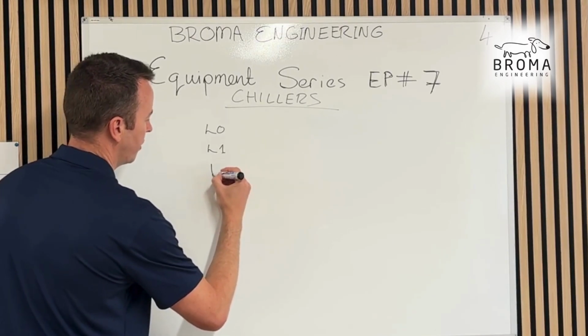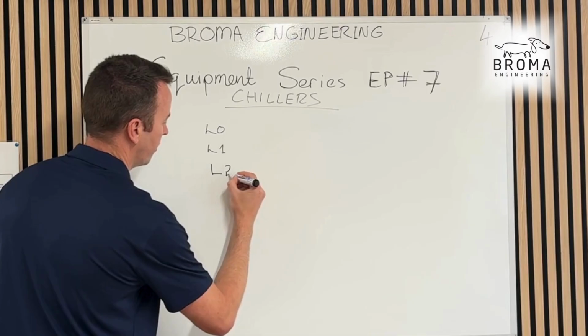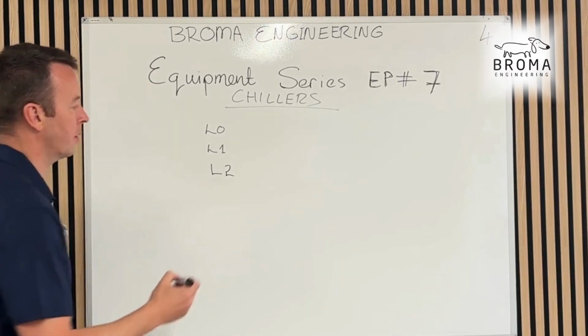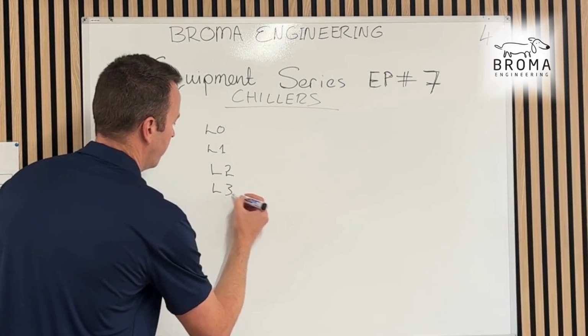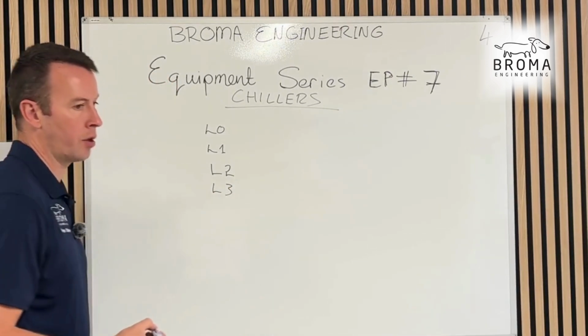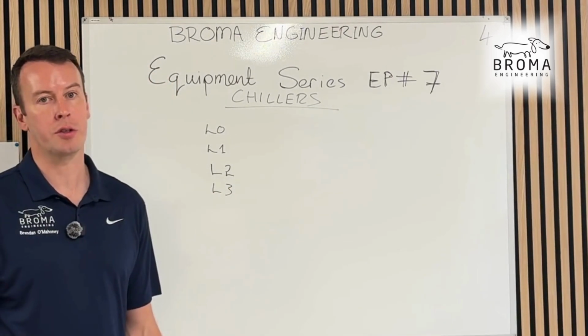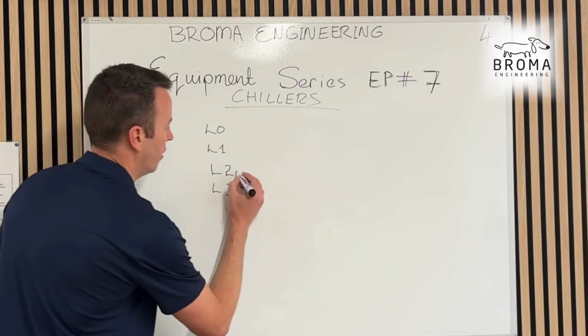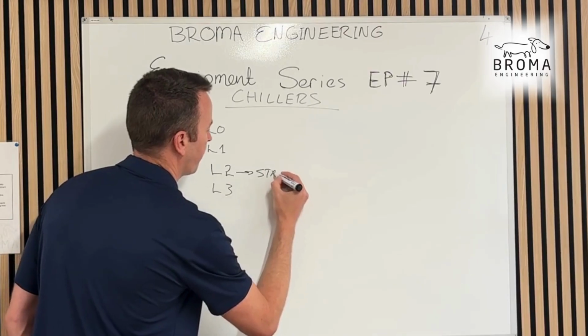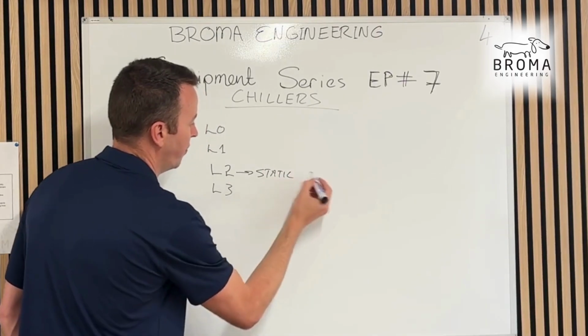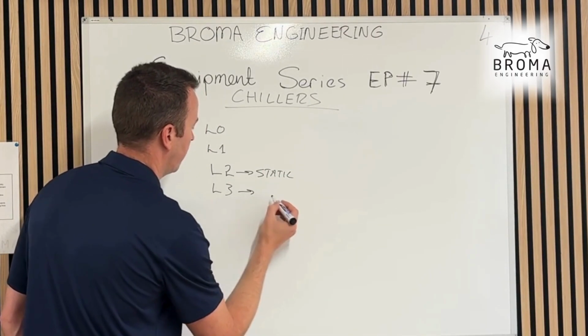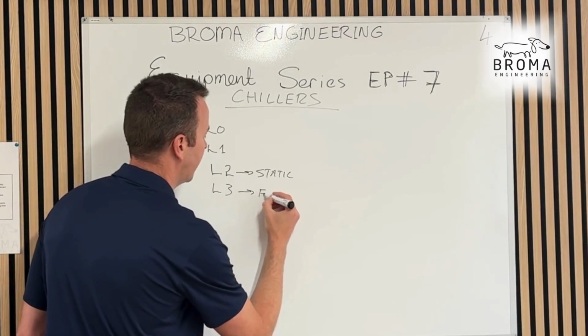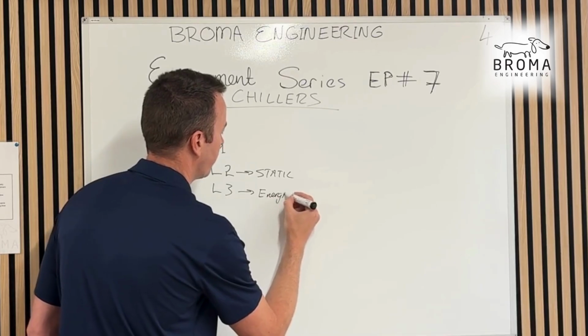Red tag now is done at delivery, so level 2 is install on site, and level 3 is what people traditionally call commissioning, but I call it energization and testing. It's dynamic. Level 2 is static, as in the equipment is static, not the stuff around it. Level 3 is energized and it's dynamic. That's how I remember it. That's the rule.